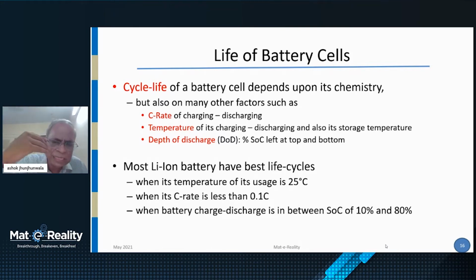If you try to charge it fully or discharge it fully, your life gets impacted. This is something not well understood, and this is what I am pointing out. Battery is best used at 25 degrees centigrade. Best charging rate is 0.1C, about 10 hours, or at least 4 to 5 hours. And best is that you operate between 10% and 80%. You may not be able to do it all the time, but keep this as the ideal, otherwise your life will go down.